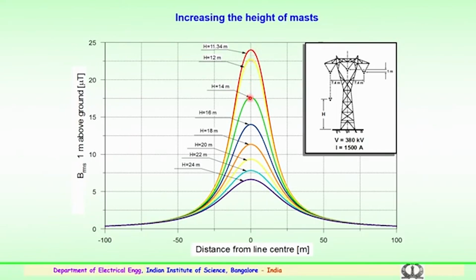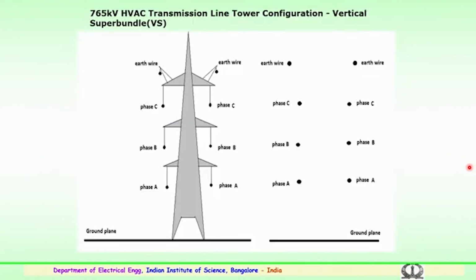As the distance increases, the magnetic field gets reduced. You can see for 14 meter, 16, 20 and so on. At a height of 24 meter, you can see the reduction from 23 micro Tesla to approximately 6 to 7 micro Tesla. So, this shows that increasing the mast or the clearances could bring down the magnetic fields, particularly the magnetic fields near the ground surface near the high voltage or extra high voltage tower, which is carrying more power. And also it should be noted that magnetic fields, as mentioned earlier, mainly depend on the current carrying capability of the conductor.